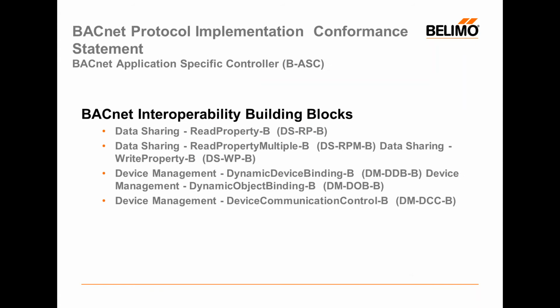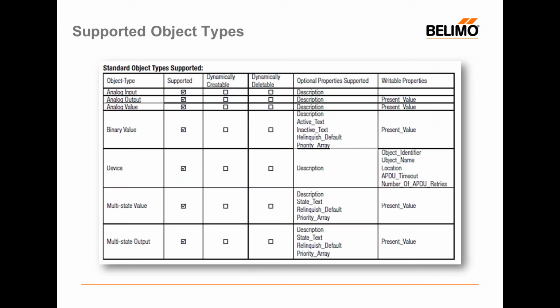In our technical document and our communications document, you will find our PICS statement, our protocol implementation conformance statement, and you can see the energy valve is a BACnet application-specific controller, and all of our read, write, and data sharing properties are going to be B. So all the property types will be B with the BACnet version of the Belimo energy valve.